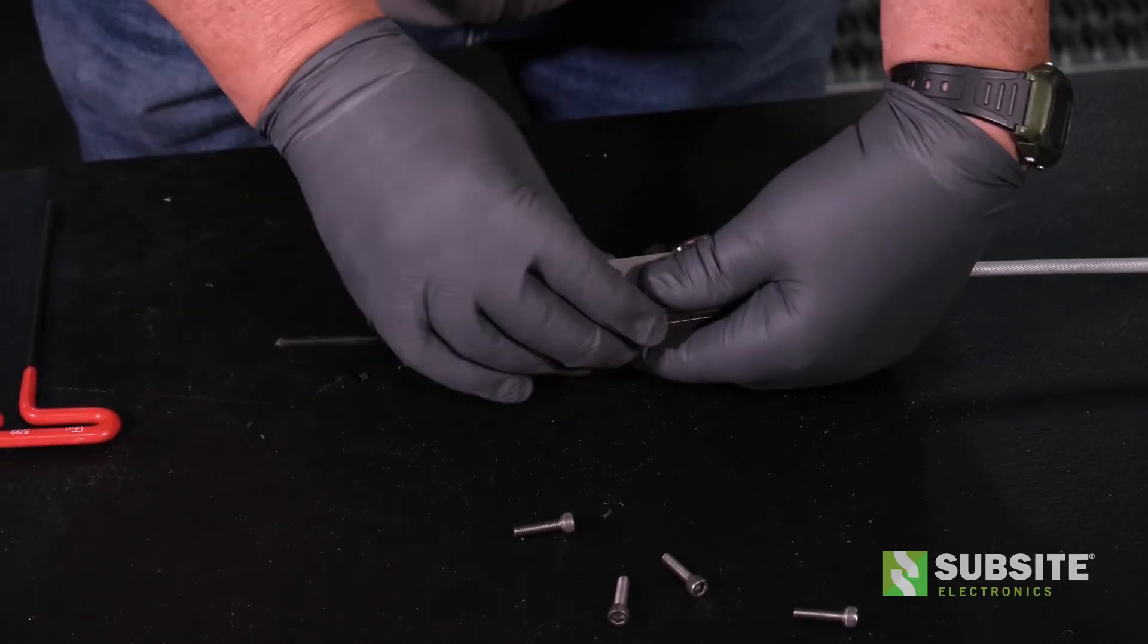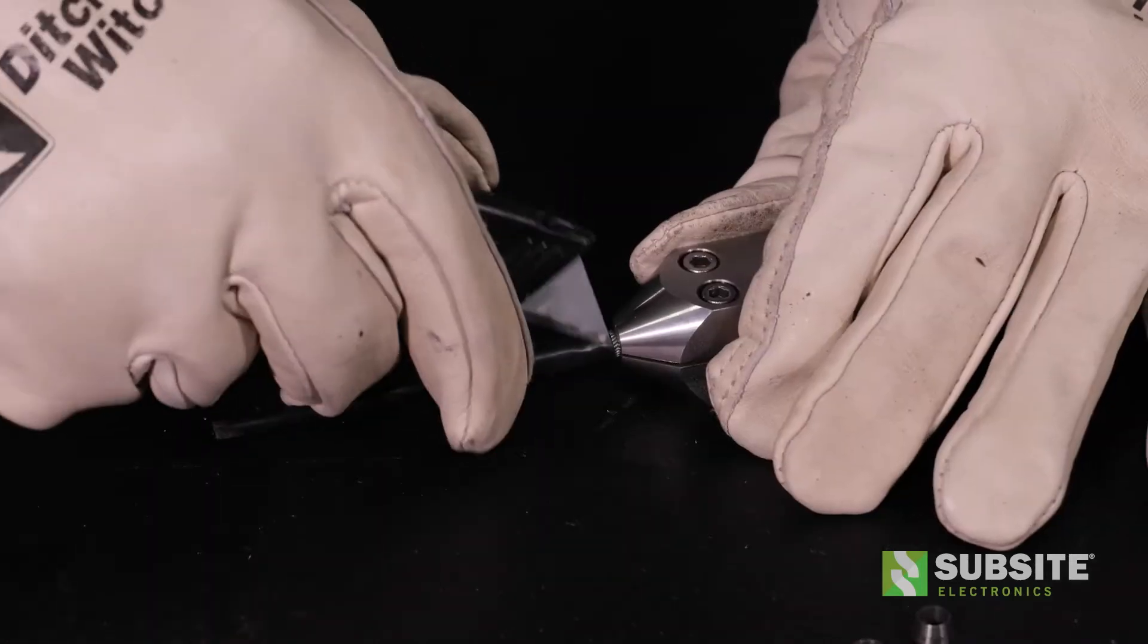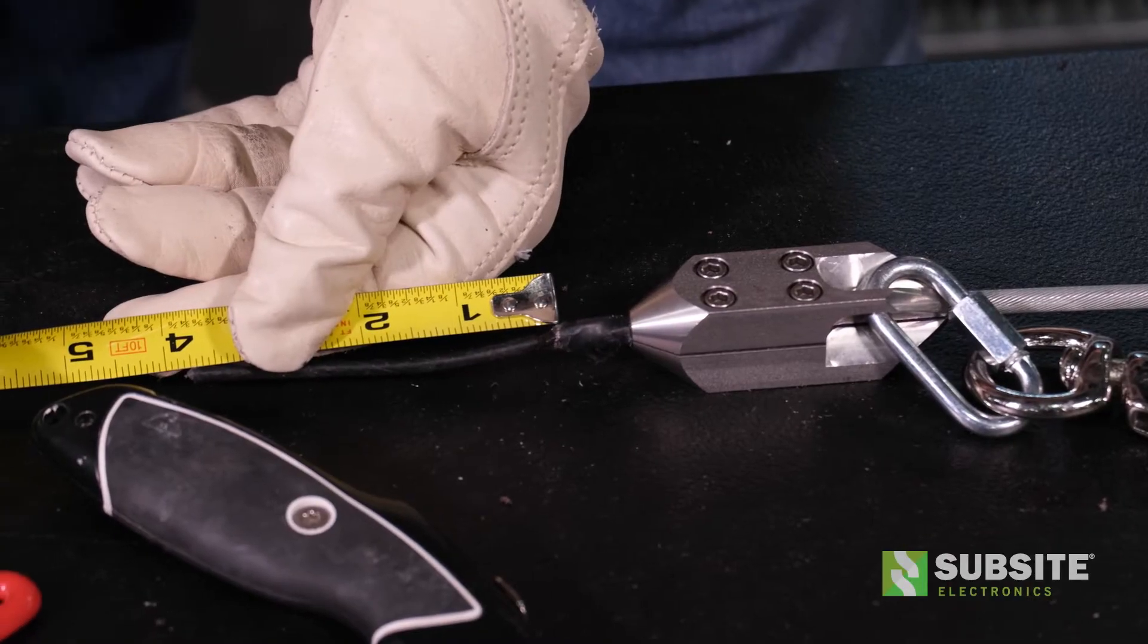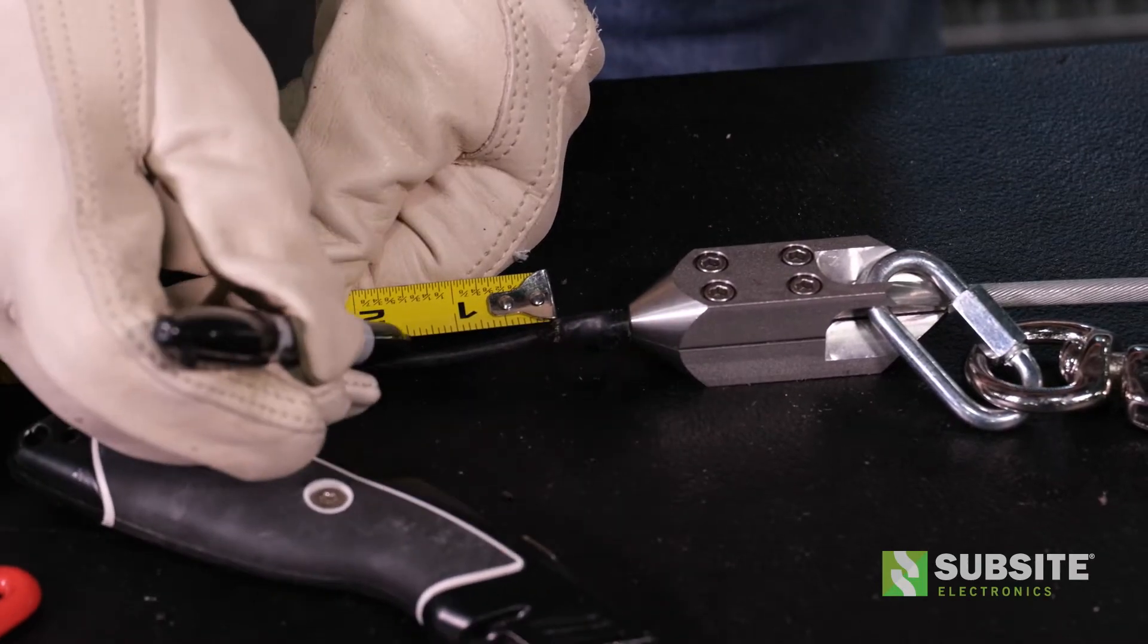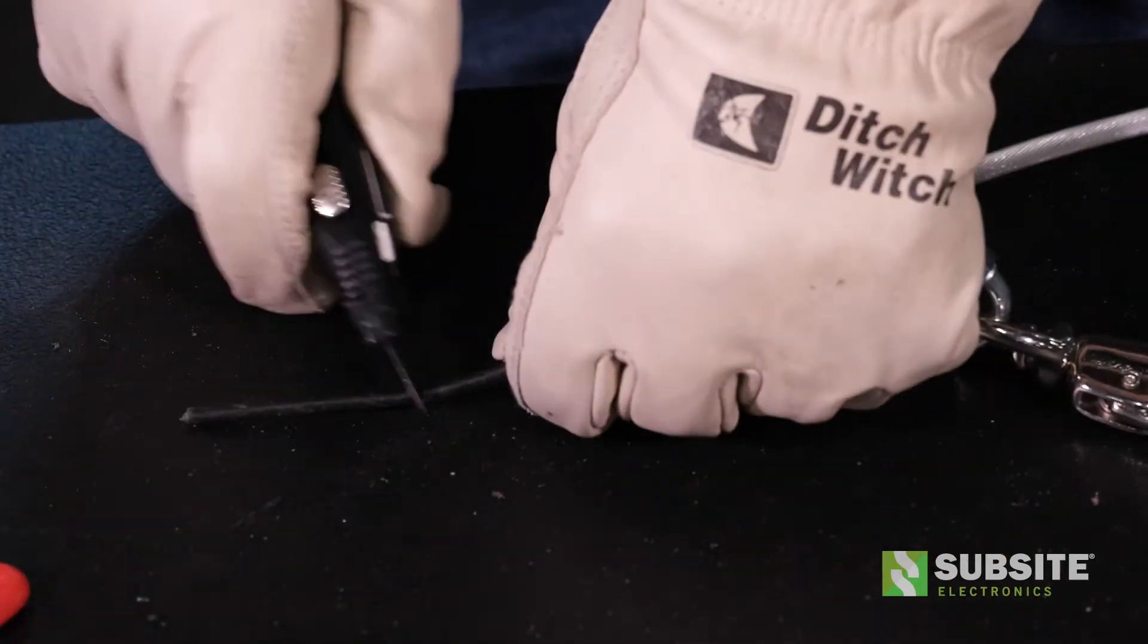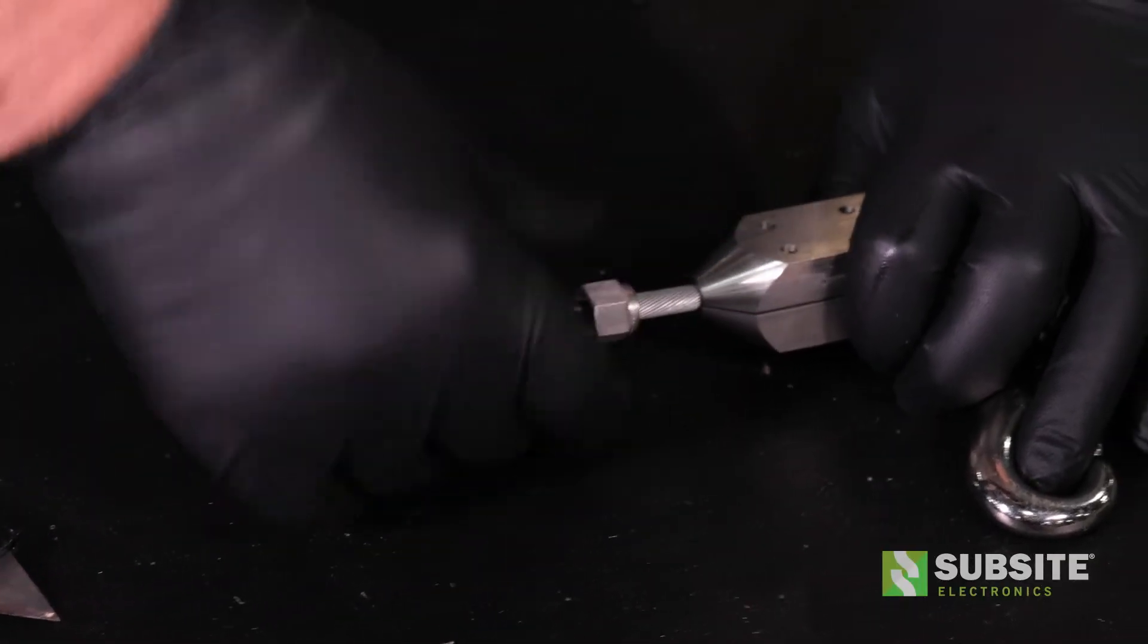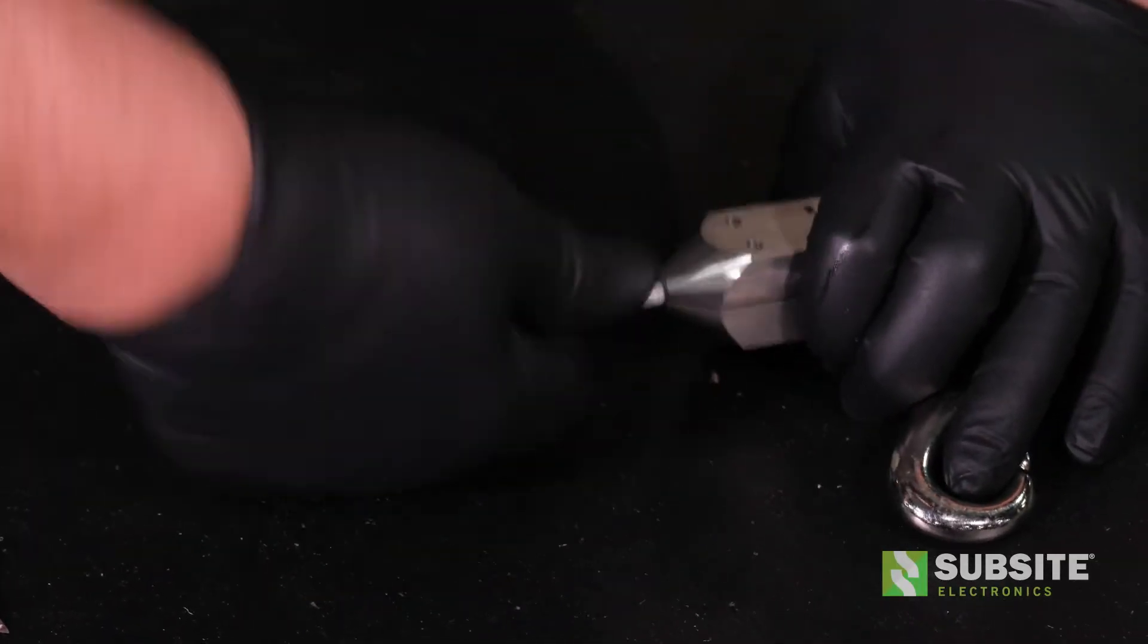Next, install the cable grip behind the black tape and remove the tape from the cable. Carefully score the black jacket 1 1/2 inches from the end of the tapered cable, taking care not to cut the cable underneath. Set the ferrule nut by turning the nut clockwise onto the cable about 1 1/2 inch.